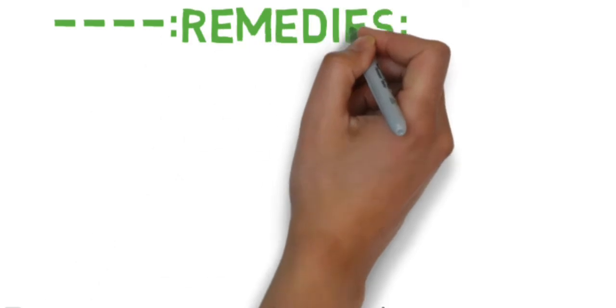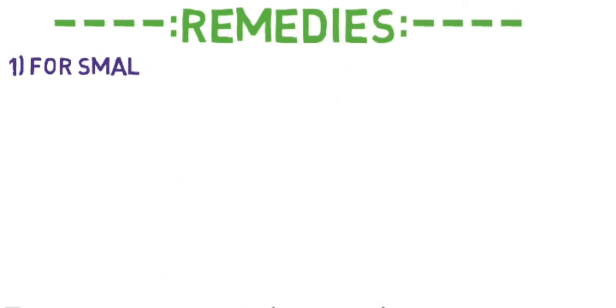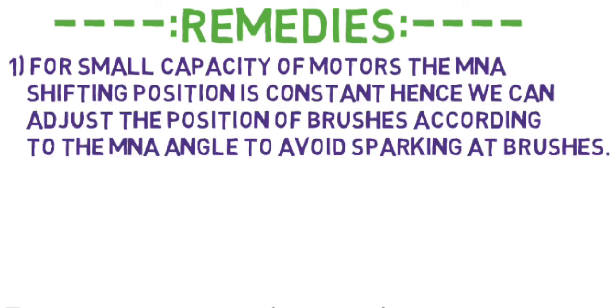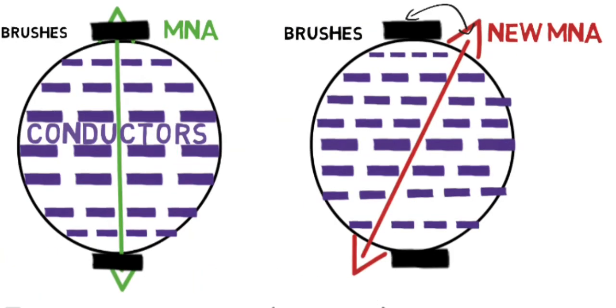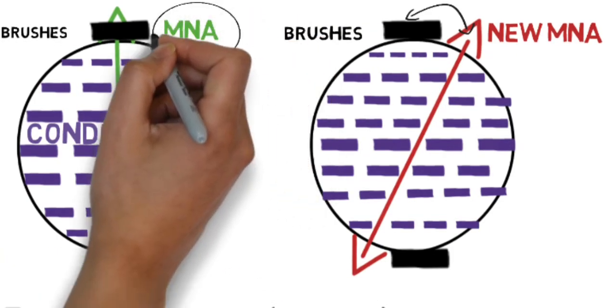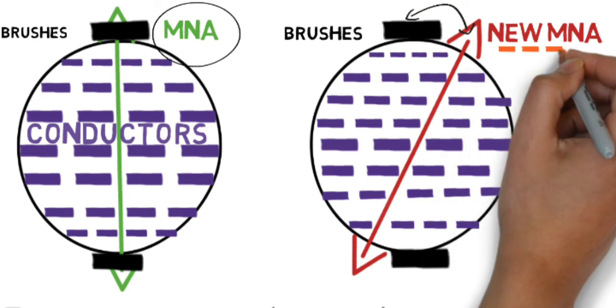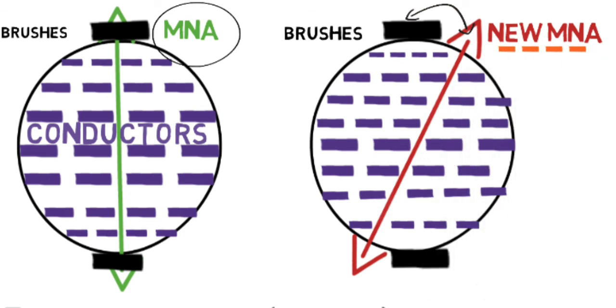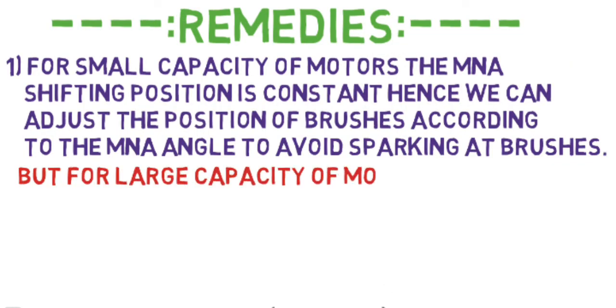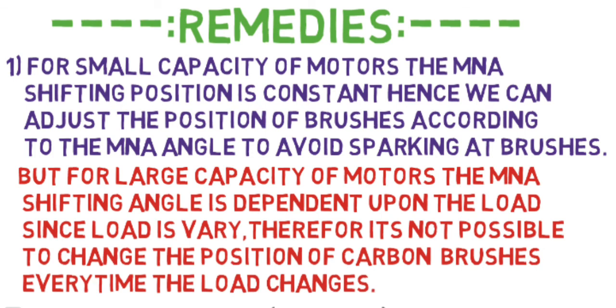The remedies for armature reaction are: First, for small capacity motors where the MNA shifting position is approximately constant, we can adjust the position of brushes according to the MNA angle to avoid sparking. Brushes are placed along the MNA, and since armature reaction shifts the MNA, we set the brush position to the new MNA to avoid sparking. However, for large capacity motors, the MNA shifting angle depends on load, and since load varies, it is not practical to reposition brushes every time.